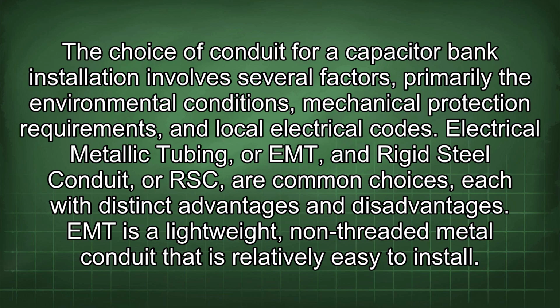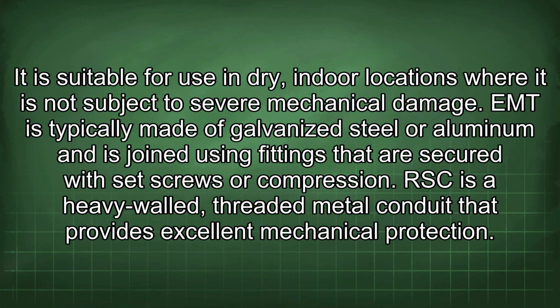Electrical metallic tubing, or EMT, and rigid steel conduit, or RSC, are common choices, each with distinct advantages and disadvantages. EMT is a lightweight, non-threaded metal conduit that is relatively easy to install. It is suitable for use in dry, indoor locations where it is not subject to severe mechanical damage.